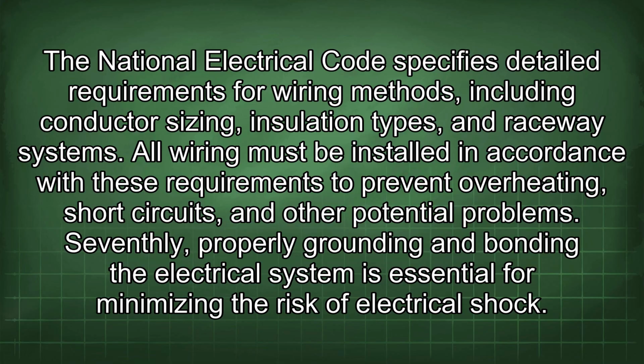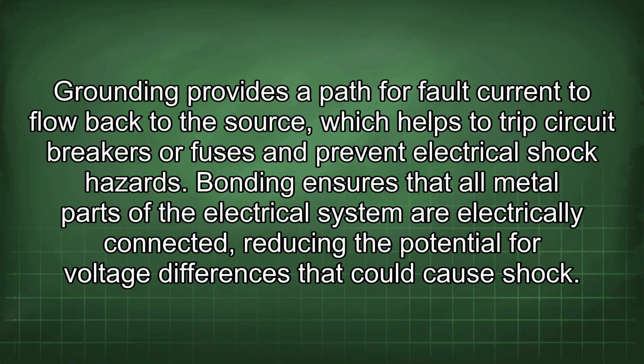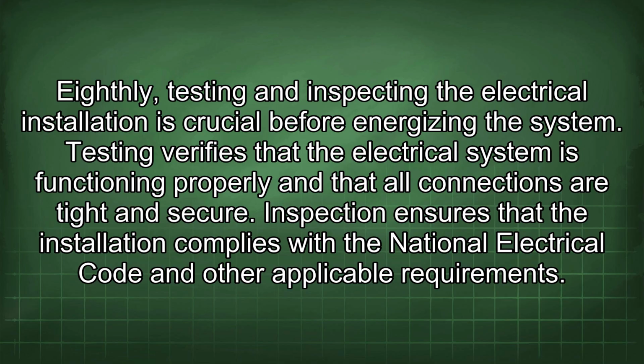Seventhly, properly grounding and bonding the electrical system is essential for minimizing the risk of electrical shock. Grounding provides a path for fault current to flow back to the source, which helps to trip circuit breakers or fuses and prevent electrical shock hazards. Bonding ensures that all metal parts of the electrical system are electrically connected, reducing the potential for voltage differences that could cause shock. Eighthly, testing and inspecting the electrical installation is crucial before energizing the system.